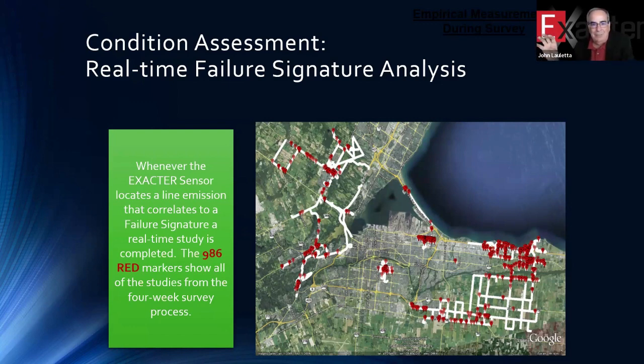Well, that doesn't mean much because there's a lot of transient events associated with the detection of partial discharge. Partial discharge can travel down the conductor, and it appears to be at the next pole as well, when it really isn't there.